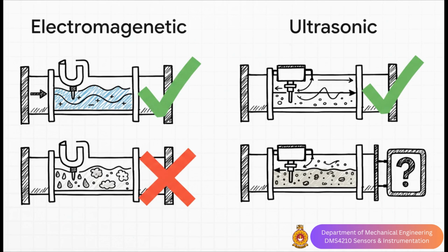So what's the trade-off? Mag meters are incredibly accurate, but the fluid has to be conductive, so they're no good for oils or pure gases. Ultrasonic sensors, on the other hand, have the amazing advantage of being non-invasive. You can just clamp them on the outside of a pipe, but their performance really hinges on the fluid having the right properties for the job.